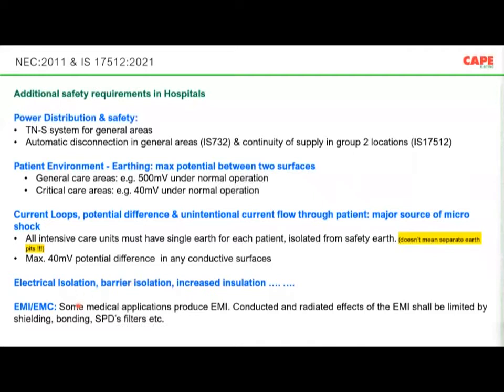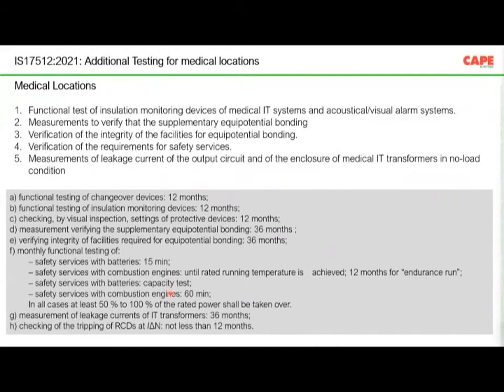EMI has to be under control, otherwise your electrical communication system will create problems. And the last one for medical locations is additional tests. In a normal electrical installation, you need to have the 10 different tests, and in the medical location, you need to have additional tests. The first one is the functional test of the medical IT system. Then the second and third are related to equipotential bonding, supplementary equipotential bonding, and main equipotential bonding. Then, the changeover system, you need to check whether leakage currents are within the limits and so on. So all these additional safety measures are also necessary.